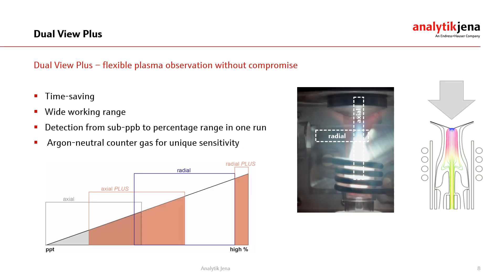The analysis of trace elements and major constituents requires different plasma observation modes and the flexibility to apply any mode to any emission line in a single method. Our dual view plus option enables free selection of the radial and axial plasma view and additionally allows use of them in an attenuated mode. With this concept it is possible to perform a synchronous analysis of contents ranging from the sub-ppb to the high weight percent. The intelligent argon neutral counter gas technology provides highest sensitivity in axial observation and allows for robust and economic trace element detection — using the argon that purges the high resolution optics to remove the plasma tail, which is known to cause spectral interferences and reduce overall sensitivity.